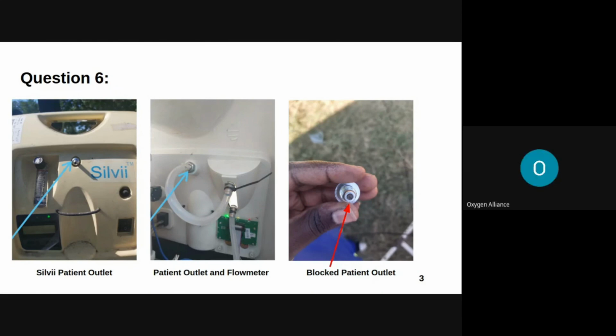All right. Thank you, Maui. The overload protector switch is a small switch or button that is found at the back of the Oxyflow 5 machine. Its function is to protect the internal electrical components against running over current or even voltage that can cause overheating and damage. So there are several things that you need to look into to find the cause of the problem. The first step we would take is to do a visual check on the wires and the components, if there are no visible faults, like in your case.